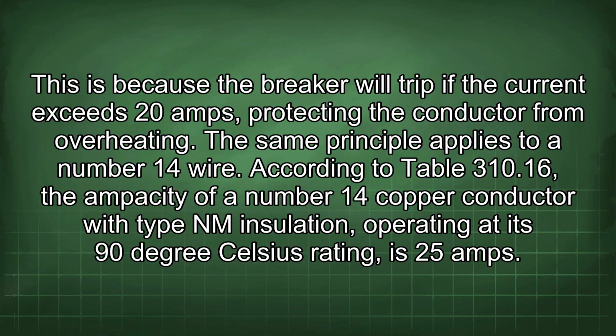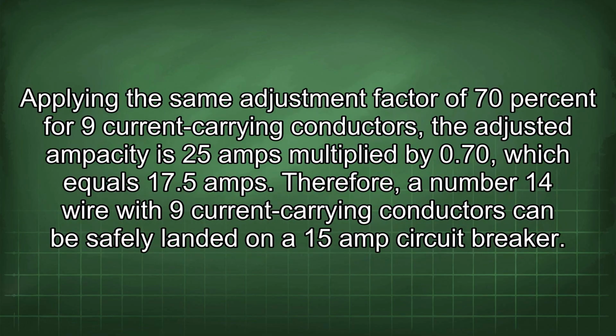The same principle applies to a number 14 wire. According to Table 310.16, the ampacity of a number 14 copper conductor with type NM insulation, operating at its 90°C rating, is 25 amps. Applying the same adjustment factor of 70% for 9 current-carrying conductors, the adjusted ampacity is 25 amps multiplied by 0.7, which equals 17.5 amps. Therefore, a number 14 wire with 9 current-carrying conductors can be safely landed on a 15 amp circuit breaker.